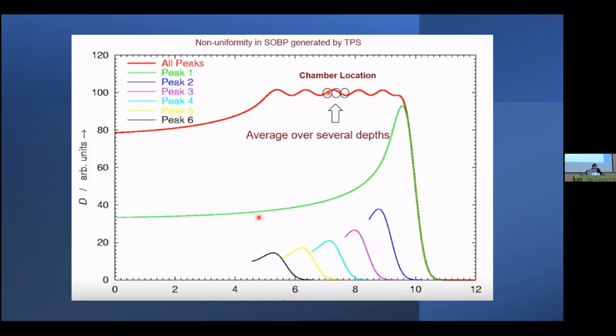And it's already hard enough making sure you're delivering the exact right thing to the patient with the CTV, PTV, everything else. When you could be really precise in the physics, you should be, so that any uncertainty is then in the actual patient delivery and anatomical changes that are happening, and not because your physics was off by 2% or such. Even though in general, when we do regulatory things, there's usually plus or minus 3%, you should be as precise as possible. But this is different than photon therapy. With photons, you go to 10 cm depth, that's your reference depth. Everything's been well characterized. It's going to be nice and flat and uniform, not necessarily in proton therapy.